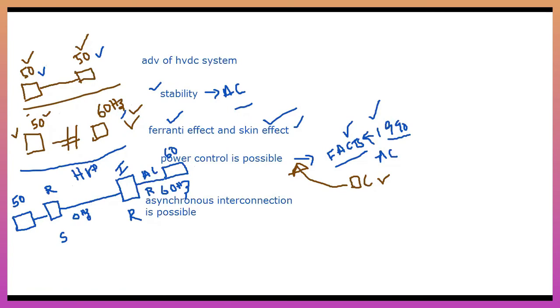Using HVDC, a 50 Hz AC system at the sending end is given as input to the rectifier and converted into a 0 Hz DC supply. Since DC has zero frequency, it is transmitted over long distances, and at the receiving end, the inverter converts the DC back into AC supply with the required frequency of 60 Hz. So systems operating at different frequencies can be connected using HVDC.